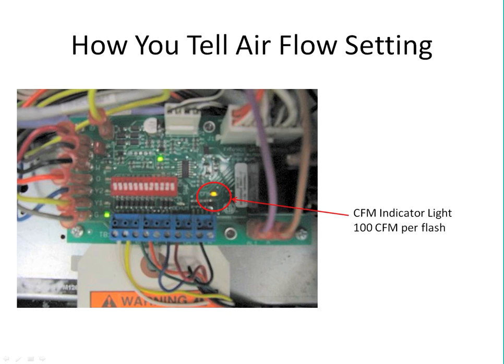One of the things you can do while you're waiting for that 15-minute runtime is on the hot water generator CFM or ECM blower board. Anytime that fan is operating, that amber light that's circled there, every time it blinks equals 100 CFM. You need to know the CFM when you're doing water side analysis, so go ahead and count the CFM, because that doesn't need to wait 15 minutes, and it kind of kills the time that you're spending there anyway. So count those blinks and write that down, and then I strongly recommend you reference the product technical guides to make sure that that is within the CFM range that it needs to be for that unit.